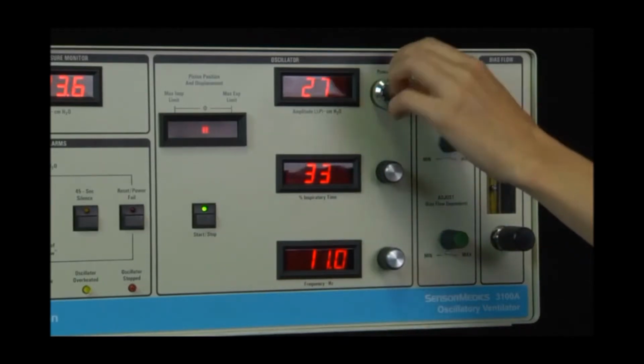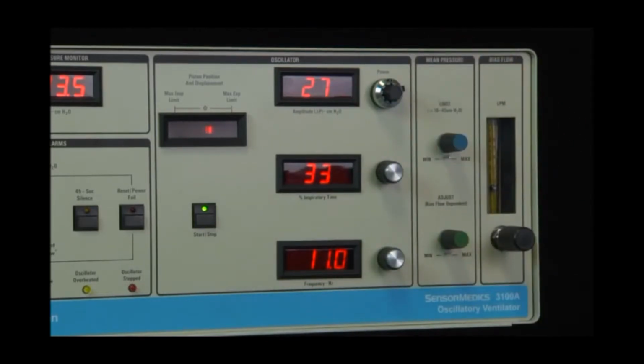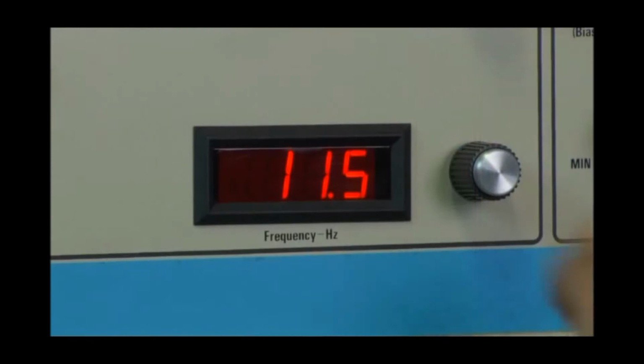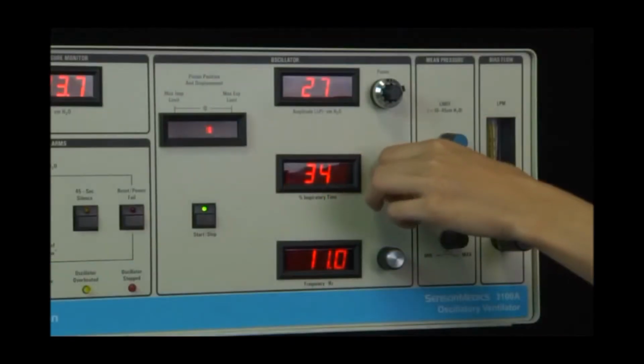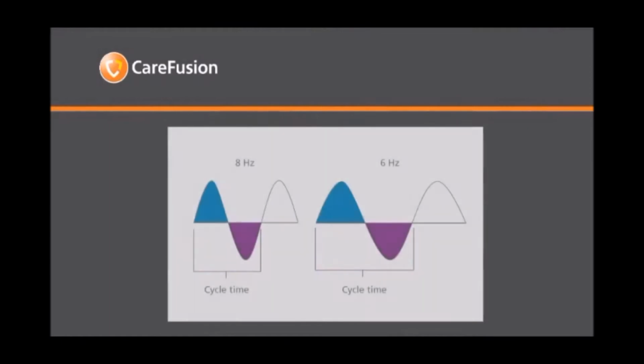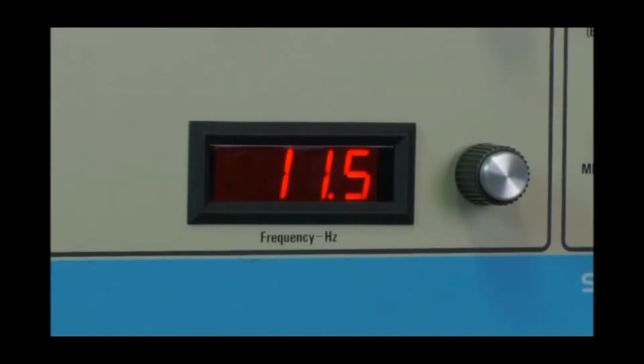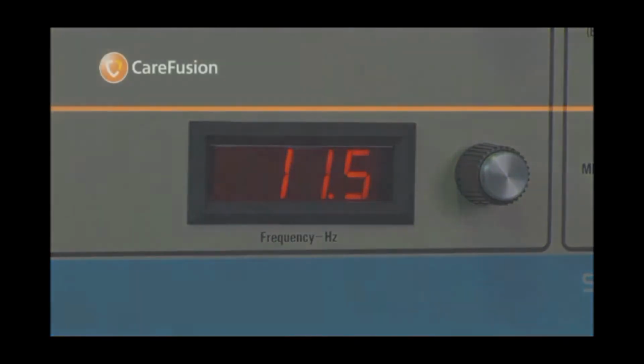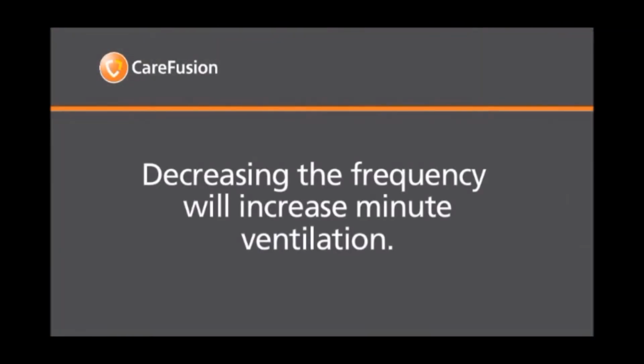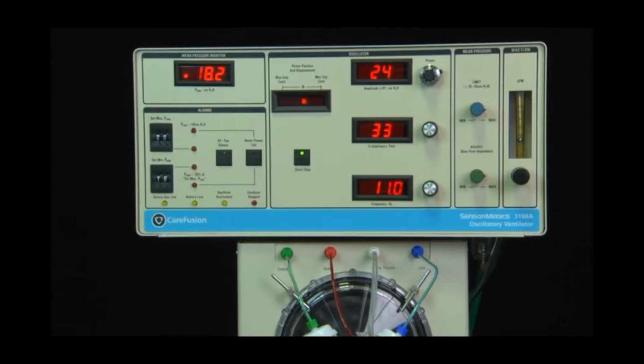Since a given power setting represents a specific electromagnetic force acting on the piston, the duration of the force is controlled first by the frequency and second by the inspiratory time percent. As frequency decreases, total cycle time increases, thereby increasing the duration of the time the force acts on the piston. This results in an increase in tidal volume. This means that the frequency behaves counterintuitively to conventional ventilation, and that decreasing the frequency will increase minute ventilation. Once an appropriate frequency is arrived at for a given patient, it usually does not change for the duration of therapy.